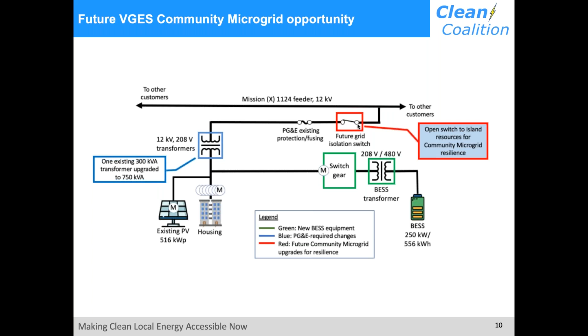So if we want to turn Valencia Gardens into a community microgrid, which it should be, remember this is a senior citizen and low income, very vulnerable population. You want to be able to shelter these hundreds of people in place rather than taking them to an emergency shelter and using beds that should go to people without an easy situation to shelter in place. The community microgrid is enabled simply by adding a grid isolation switch, shown here in red. If the broader grid goes down, you open that switch and make sure the solar and storage work together to serve at least the most critical loads at the Valencia Gardens Apartments.